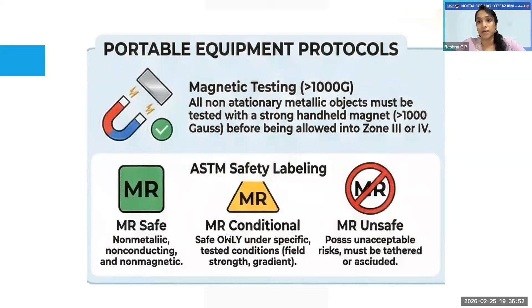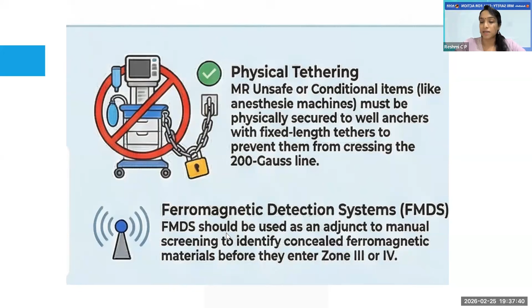Physical tethering is an important concept explained in the new ACR guidelines. All MR unsafe or conditional items, especially the anesthesia machine, should be physically secured and anchored in zone 3, and should not enter zone 4. If kept in zone 3, it should be properly anchored. So physical tethering is very important for these MR unsafe or MR conditional items. We should also use a ferromagnetic detection system. We can also use a handheld magnet to check the patients and any portable machines or devices before entering zone 4, the MR room.